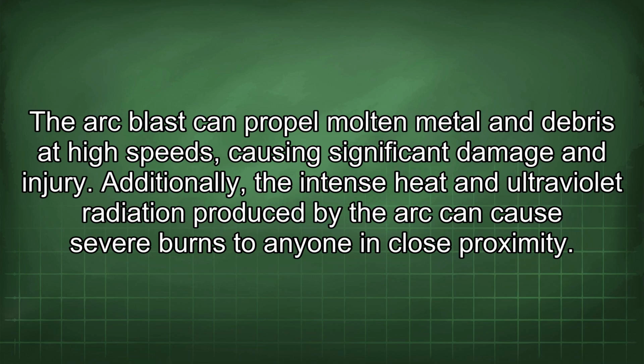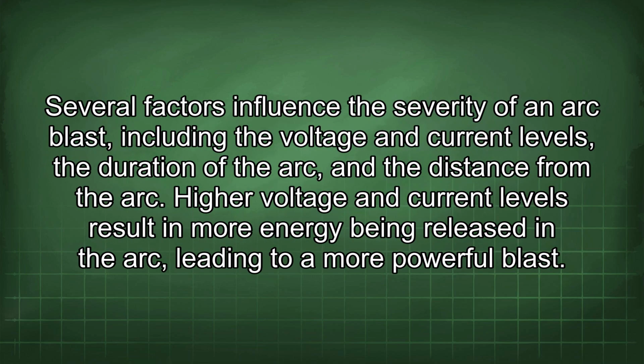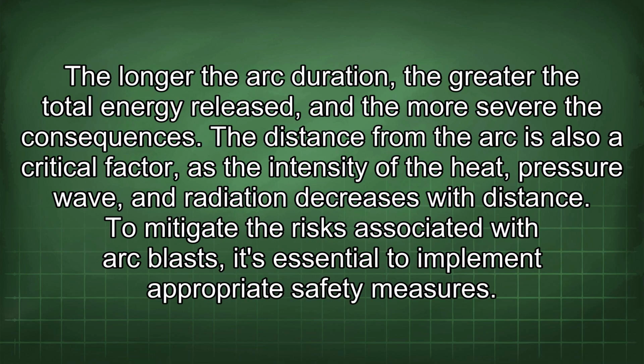The arc blast can propel molten metal and debris at high speeds, causing significant damage and injury. Additionally, the intense heat and ultraviolet radiation produced by the arc can cause severe burns to anyone in close proximity. Several factors influence the severity of an arc blast, including the voltage and current levels, the duration of the arc, and the distance from the arc. Higher voltage and current levels result in more energy being released in the arc, leading to a more powerful blast. The longer the arc duration, the greater the total energy released, and the more severe the consequences. The distance from the arc is also a critical factor, as the intensity of the heat, pressure wave, and radiation decreases with distance.